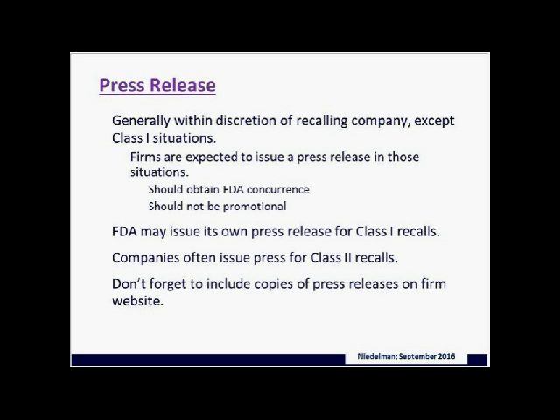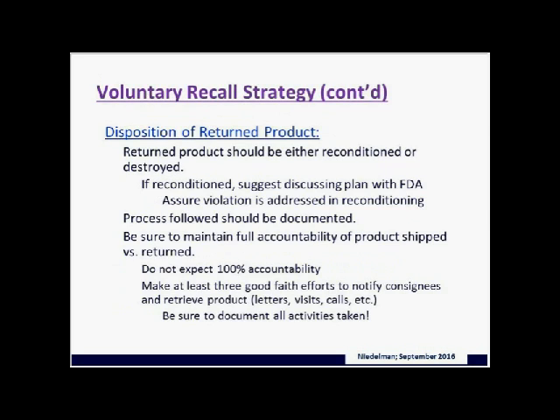FDA will not ask for your input on their press release, so make sure it's in your best interest to do it right the first time and take FDA suggestions. Don't try to shortcut it or change promises as it goes forward. Again, keep those on your website as well. The returned product as a result of the recall should either be reconditioned or destroyed. If you're going to recondition it, I suggest you get that plan approved by FDA before you go through the expense only for them to disapprove it.